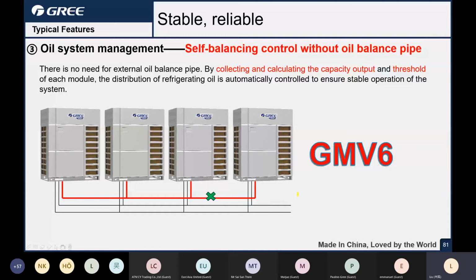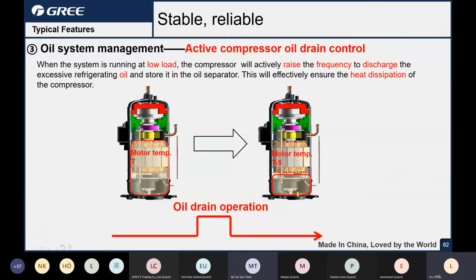And for GMV6, another good news is it cancels the oil balance pipe. That's really good for your installation. No need to install the oil balance pipe anymore. Okay, because of the technology I introduced previously, the oil balance pipe is no longer needed. For the compressor, another control is the active compressor oil drain control.